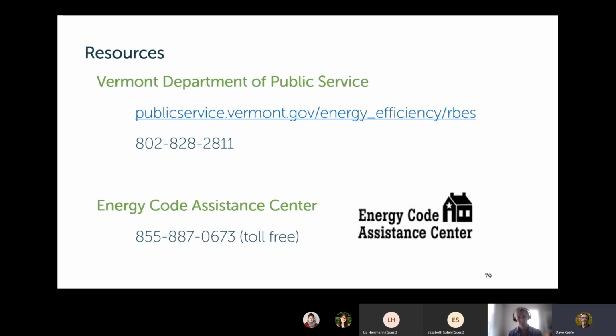And under the code we're in as of today, that's an acceptable alternative. So you either do the blower door test or you do the checklist. On September 1st, when the new code kicks in, the checklist will go away. That's no longer an option. Now you'll have to do the test.